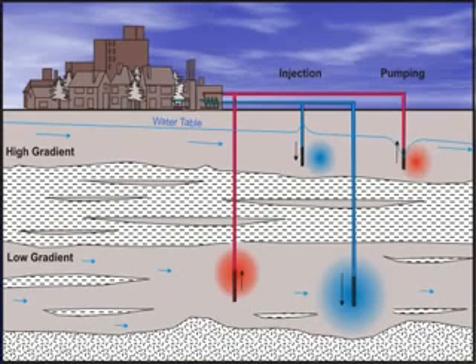If you have a low gradient, such as in this example, you can keep the hot and the cold plumes close together or close to the well. But if the gradient is fairly high and you have rapid flow of water, then those plumes that you're trying to create will actually migrate down gradient and away from your well. So you have to determine the geological and hydrogeological characteristics of your site. In this example, these little open lenses here are potentially small aquifers that are not areally extensive, but they might be suitable if you've got a small application.